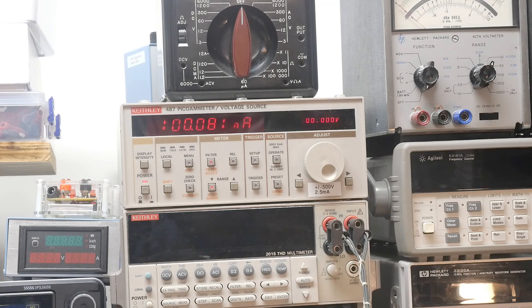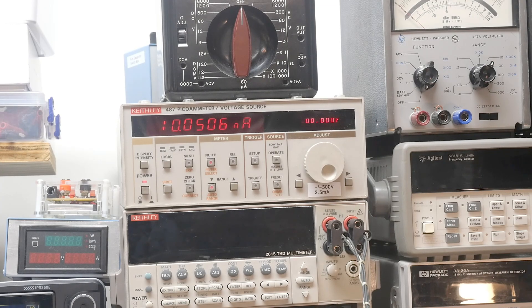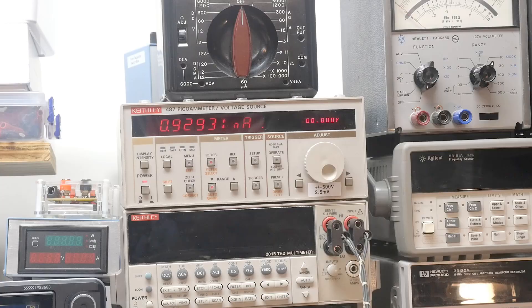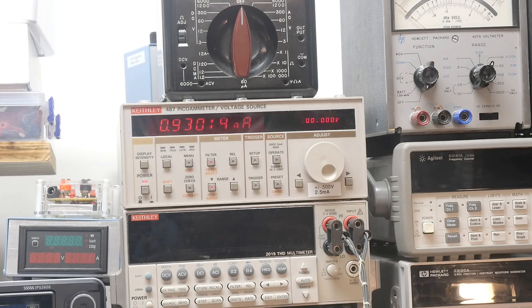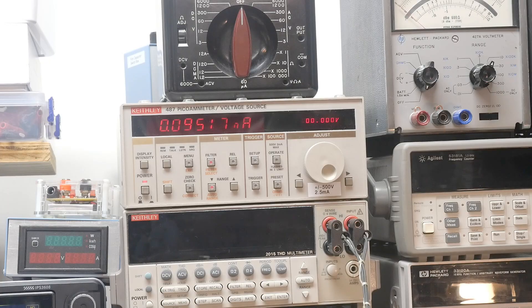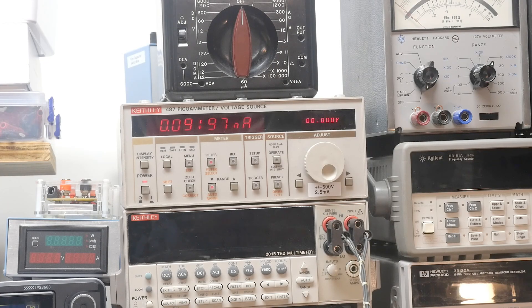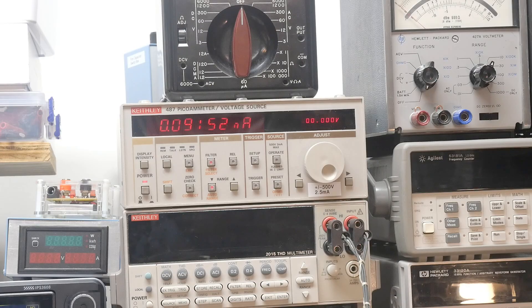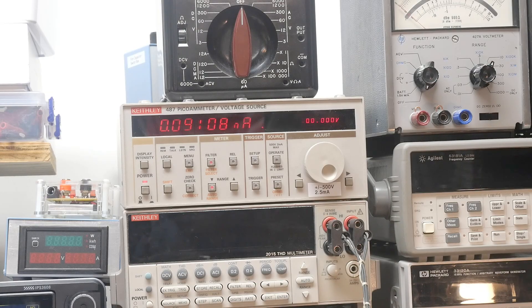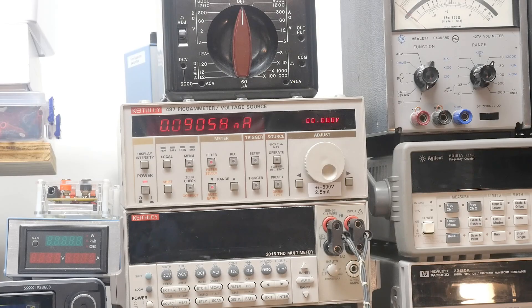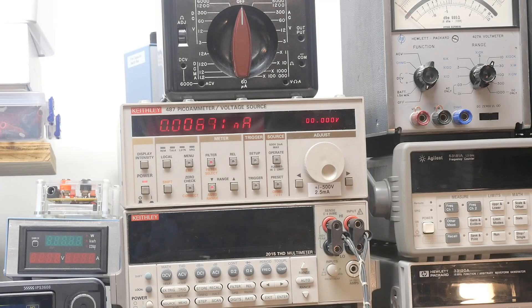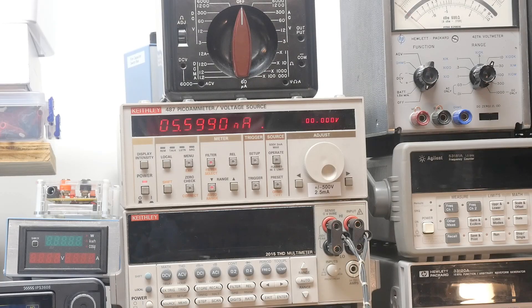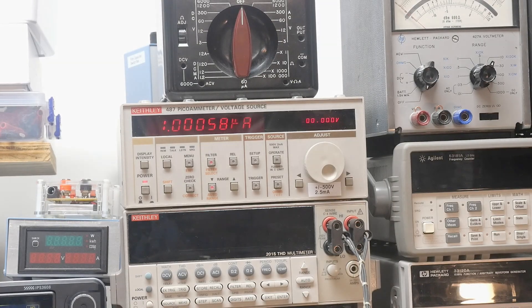And yeah we got some pretty good stuff down here - it's very reliable down to 10 nano amps and 1 nano amp at 7% out, I could live with that. 7% out here at 100 pico amps, and here is 10 pico, yeah it's kind of flaky down there. Anyway pretty cool machine, I like it.